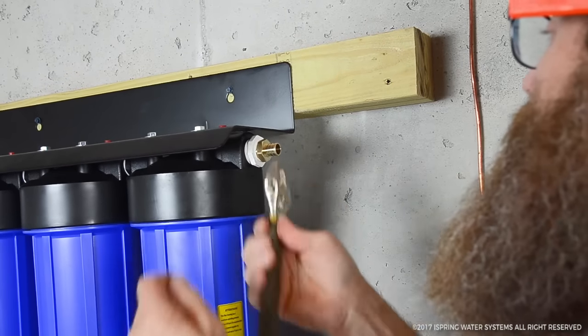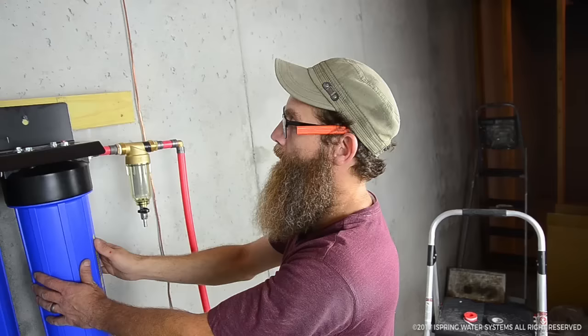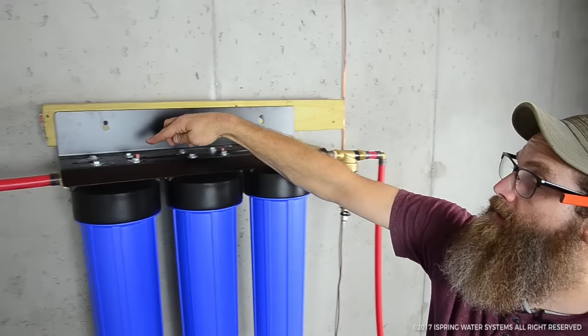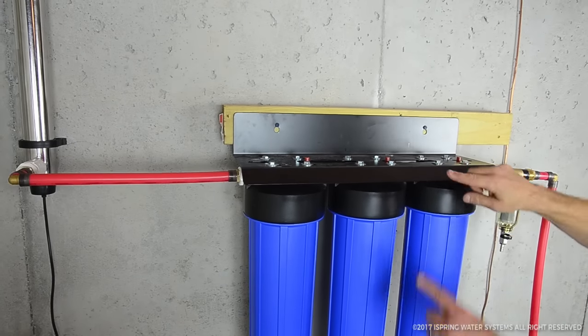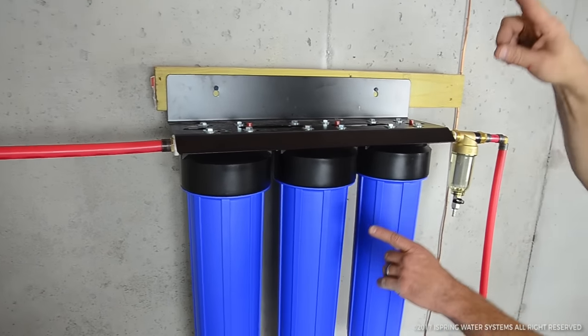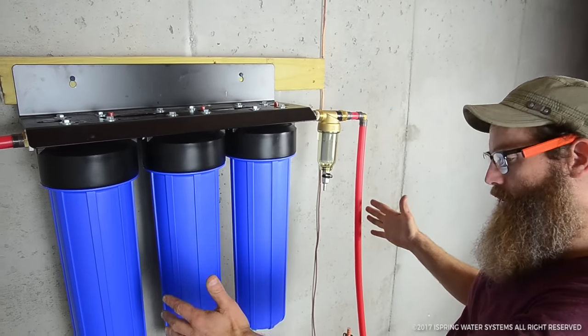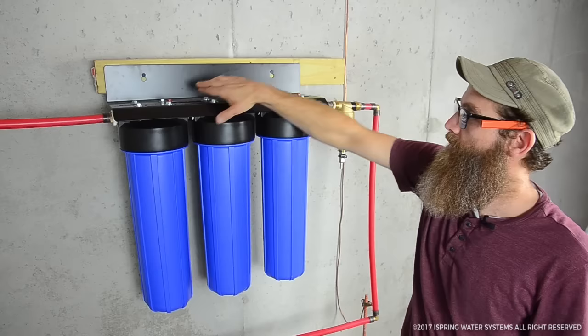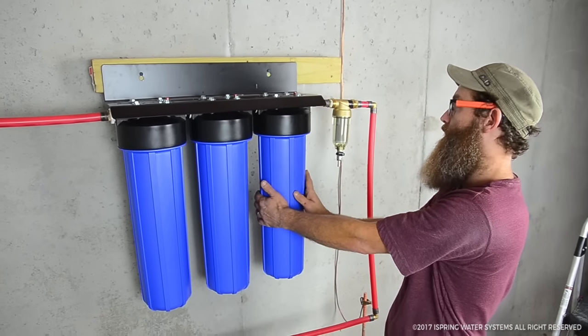When we do change these filters out, before we unscrew this, there's a pressure relief button here and here and here, and that will release the pressure that's inside of this closed loop system. There's just a small closed loop here that has pressure still on it and we just release it with those buttons and then this just comes off.